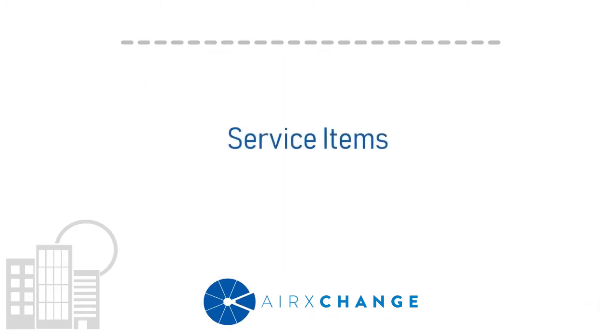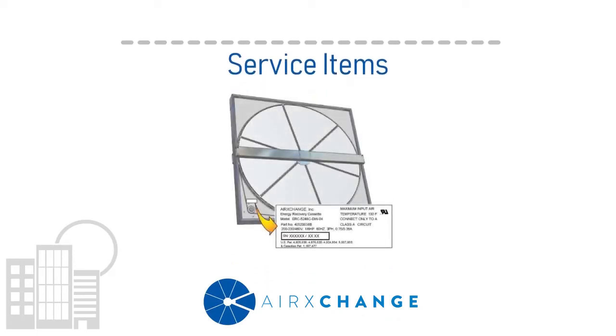So preventative maintenance for Airxchange wheels is predominantly observation and cleaning. So what happens if during the checklist process you discover a service item like a failed motor or belt or missing seal? Unlike older monolithic wheels, Airxchange designs are modular in nature, so you only have to service what needs servicing. Each energy recovery wheel is given a unique serial number that is located on a nameplate that is right above the pulley.